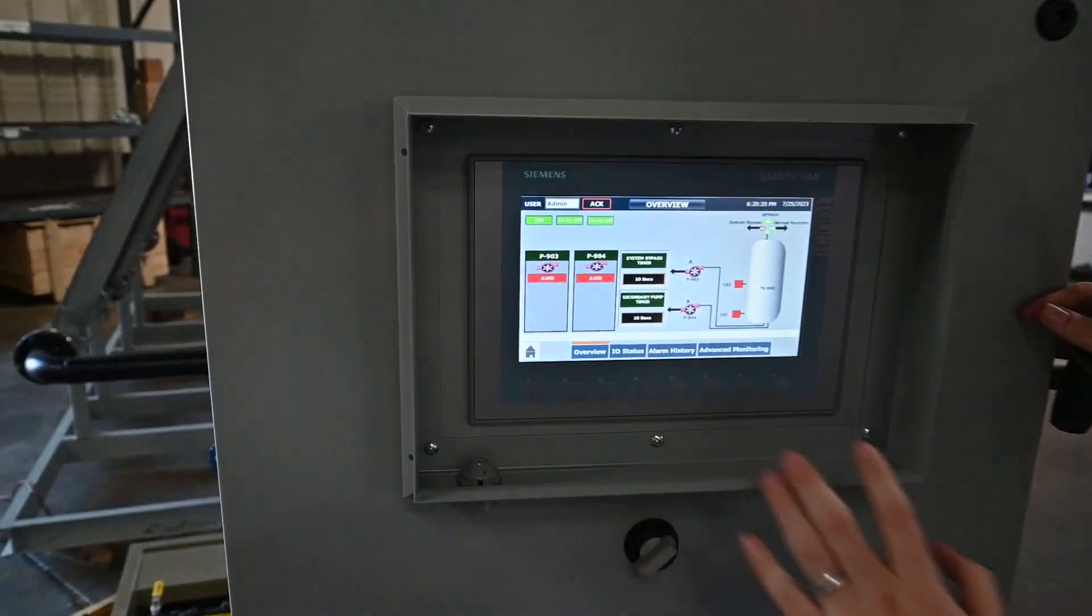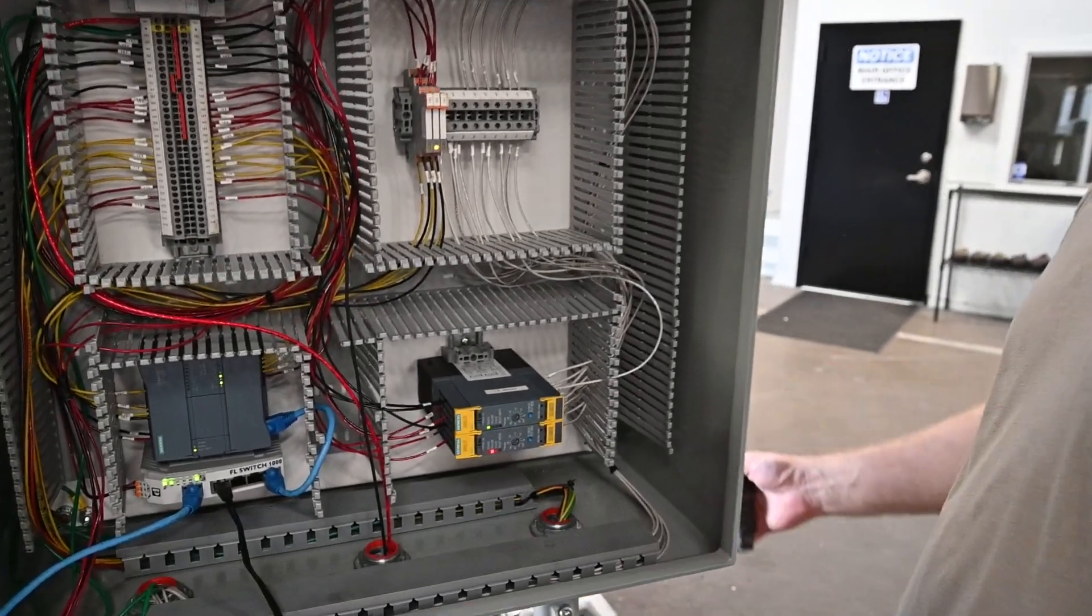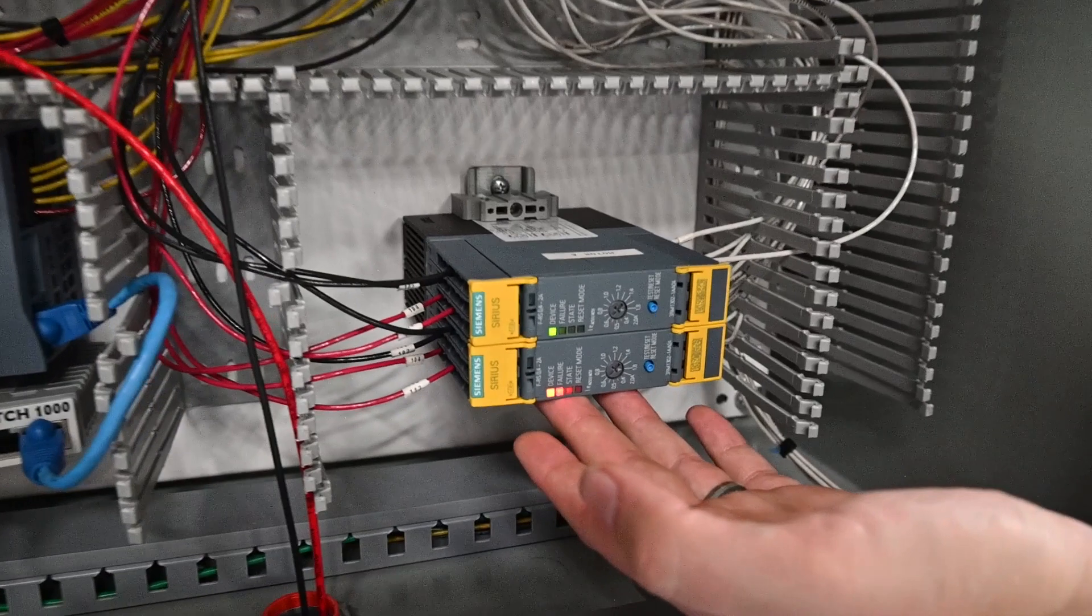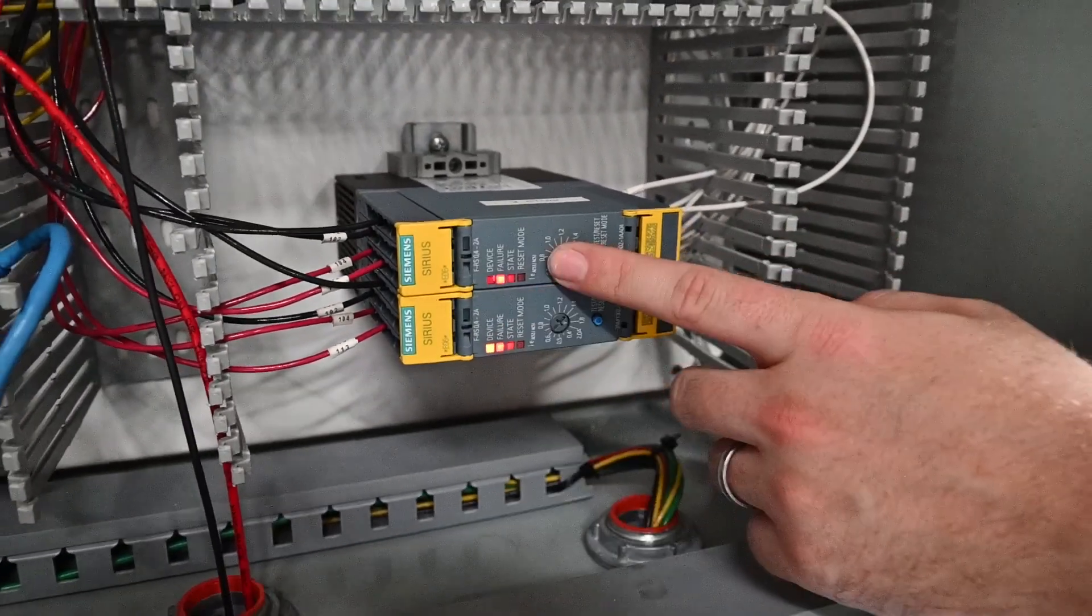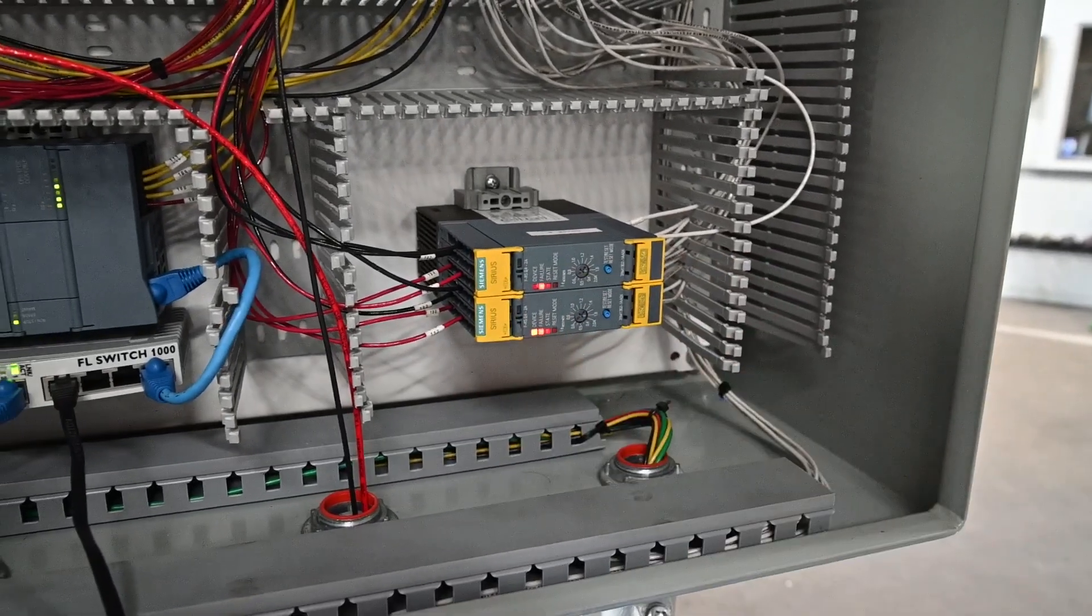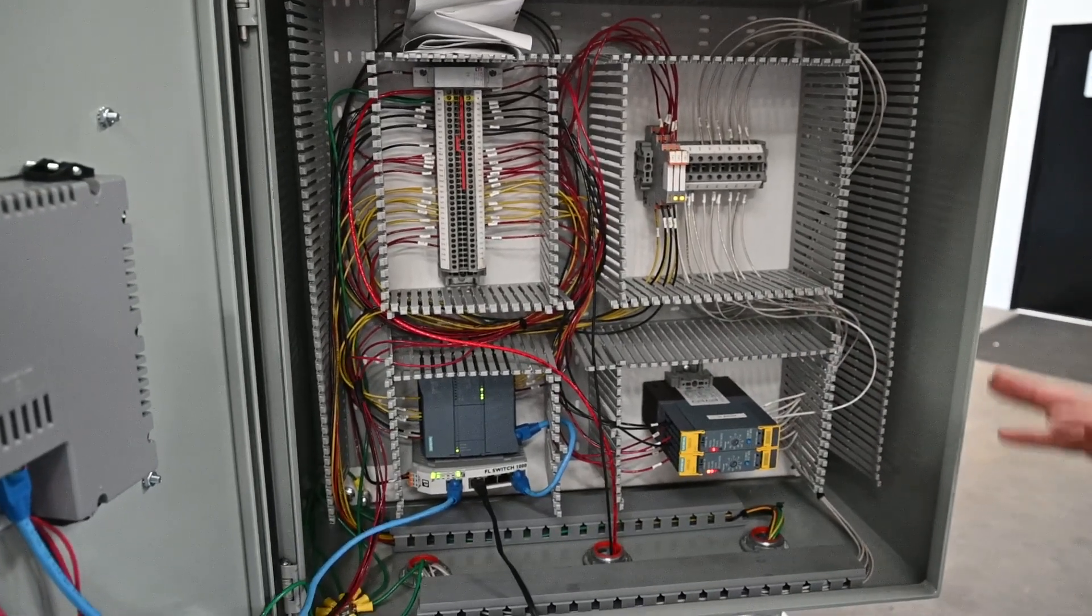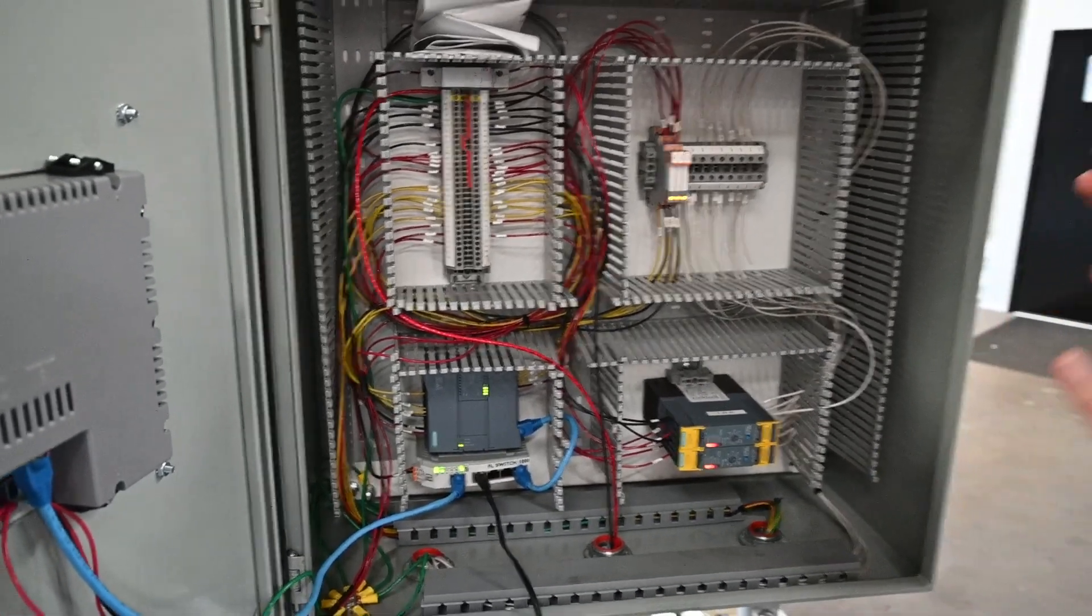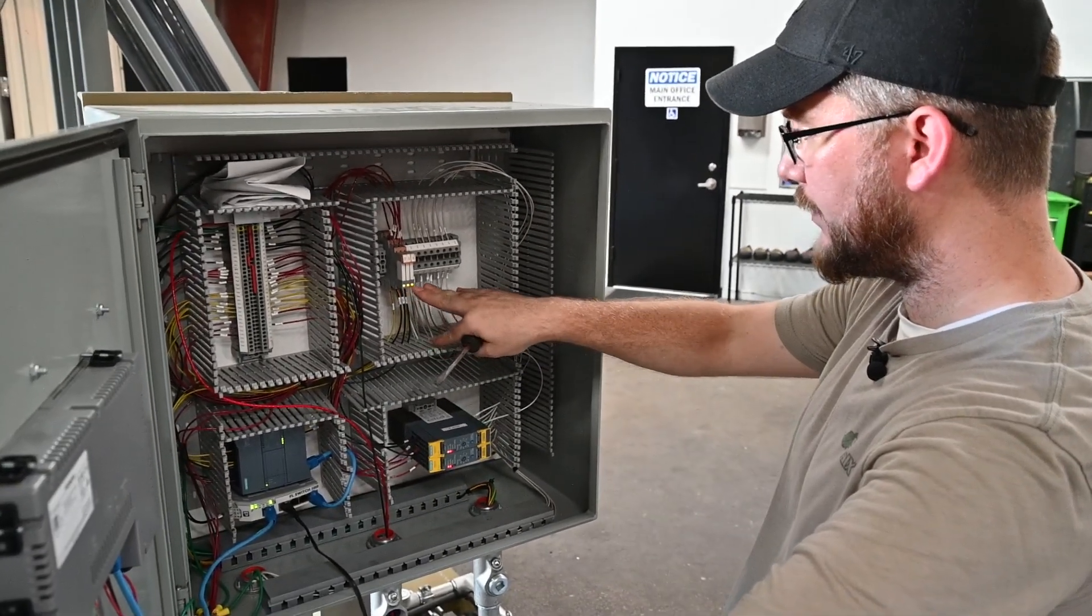So we say here the pump should be on. We don't have power running through the pumps, so it says okay, this should be on, but we're not getting the required power. And then you just have the 10 second response time for the second pump, it just went off as well. So lots of control in here, lots of monitoring and letting you know when something is not doing what it's supposed to be doing. And you see the dry contacts are there.